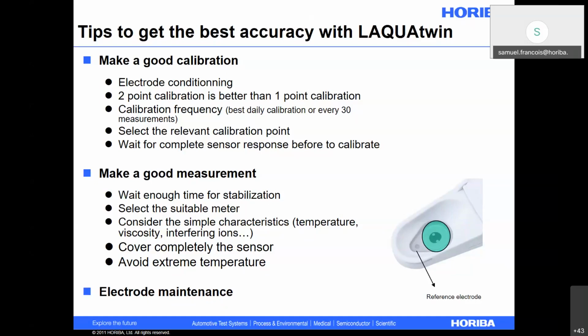Also, it's important to select the relevant calibration. This is more general, not so much for agriculture, but for example, in agriculture, for nitrate, we will be measuring concentrations in 1,000 plus up to 10,000 ppm. But if we want to do nitrate measurement in drinking water, the maximum concentration is 10 milligrams per liter. So if we calibrate our meter with the two solutions that come with the meter, 150 and 2000 ppm, it's not a really relevant calibration point to measure water.